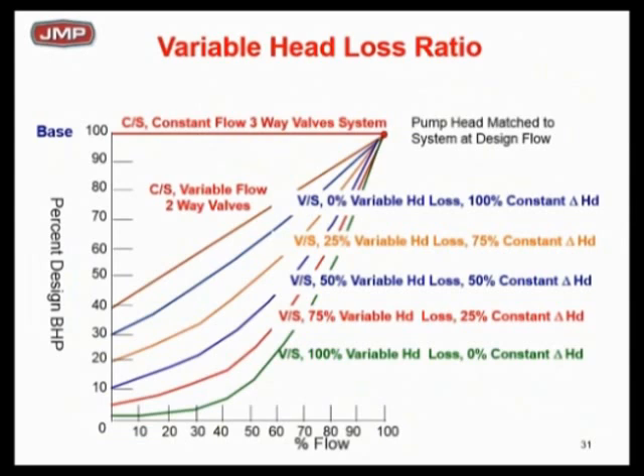Let's stay at 50% flow, because 50% flow is going to be the best majority of the time — half load, heating load, cooling load, half flow. Let's look at the real world where we live most of the time. Going to 75% variable head and 25% constant, on the red line at 50% flow, I'm up to about 25% brake horsepower. You can see what's happening as I change that ratio.